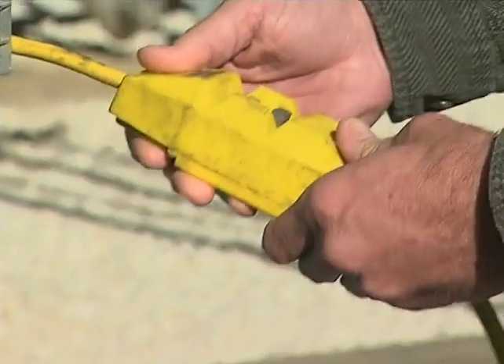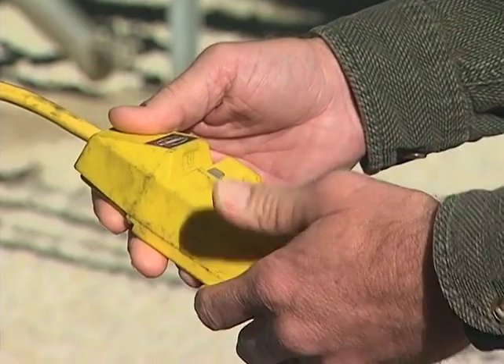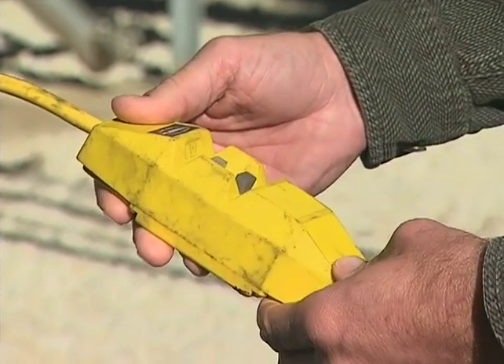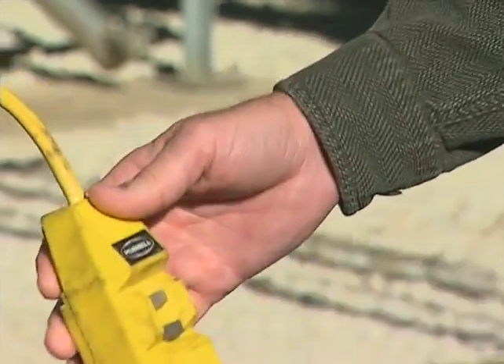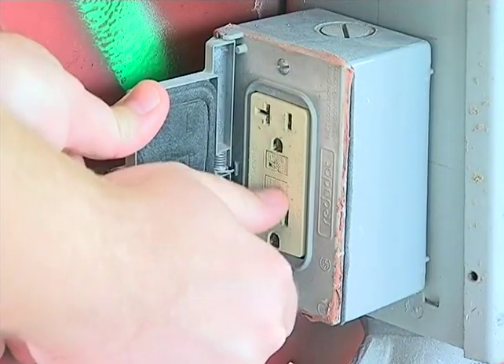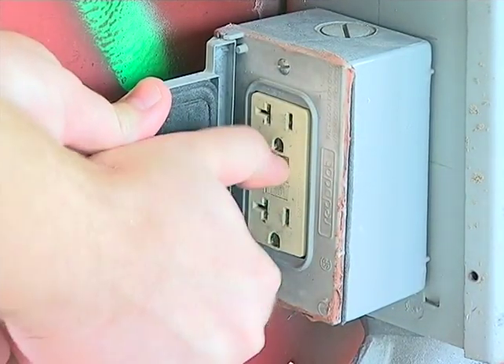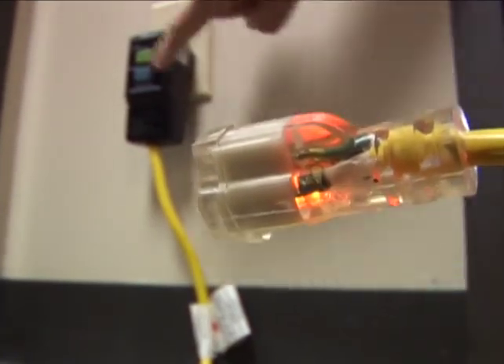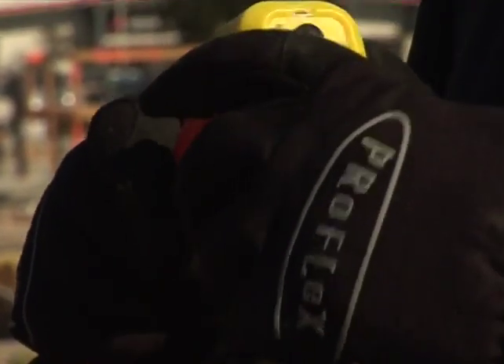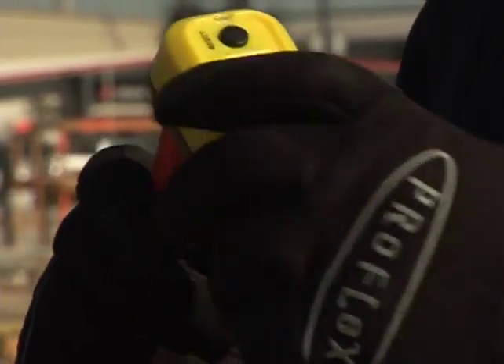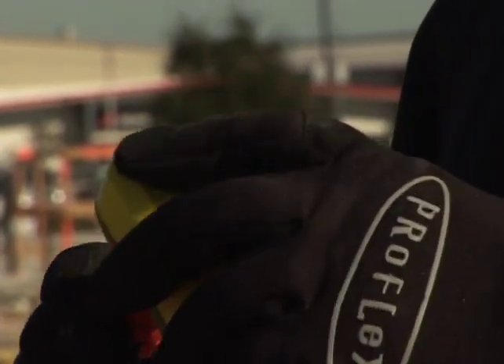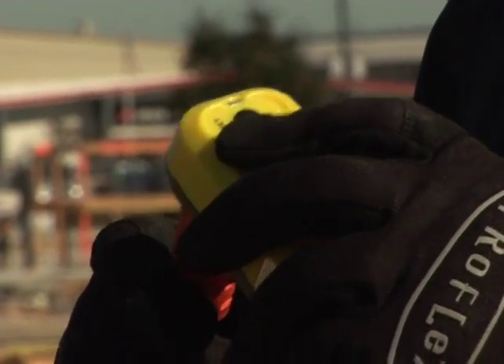GFCIs monitor the current to the load for leakage to ground. The GFCI must be tested on a regular basis. Permanently wired devices should be tested monthly, and portable type GFCIs before each use.